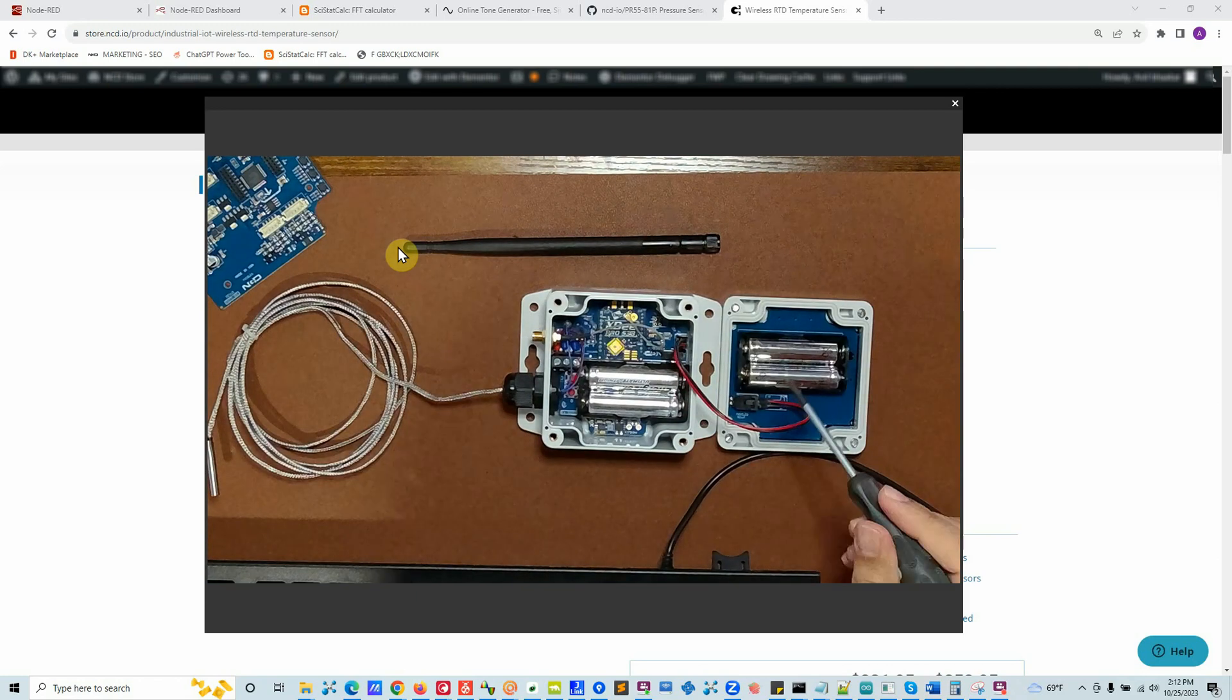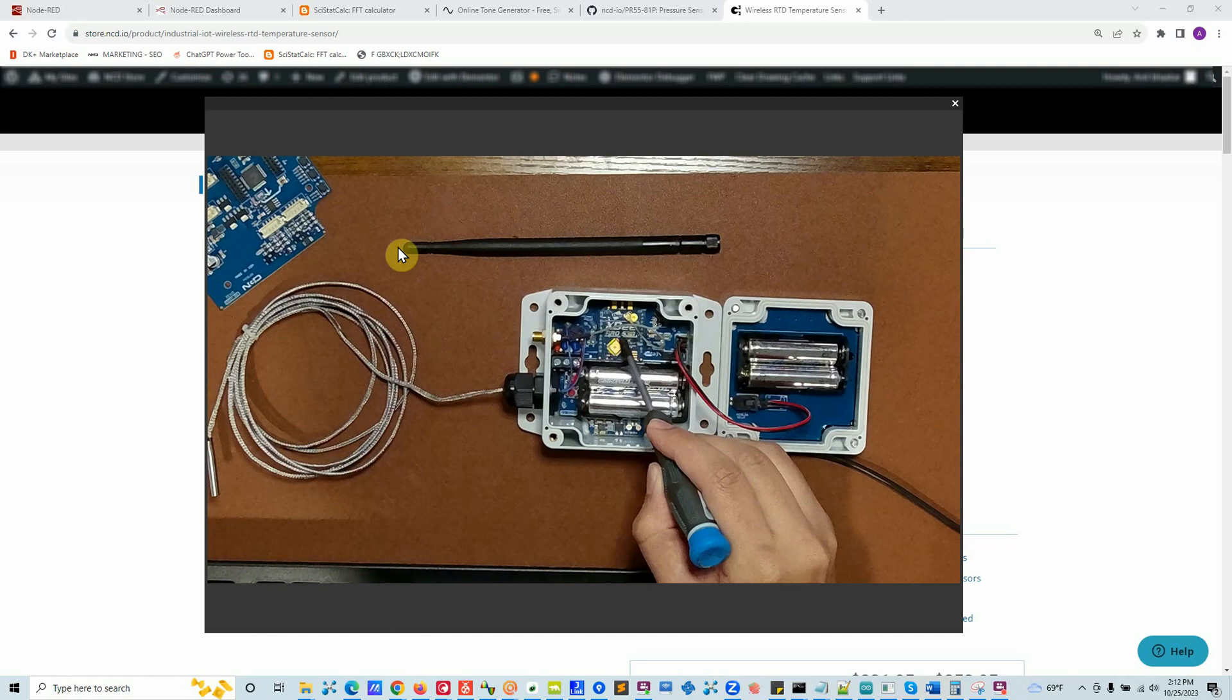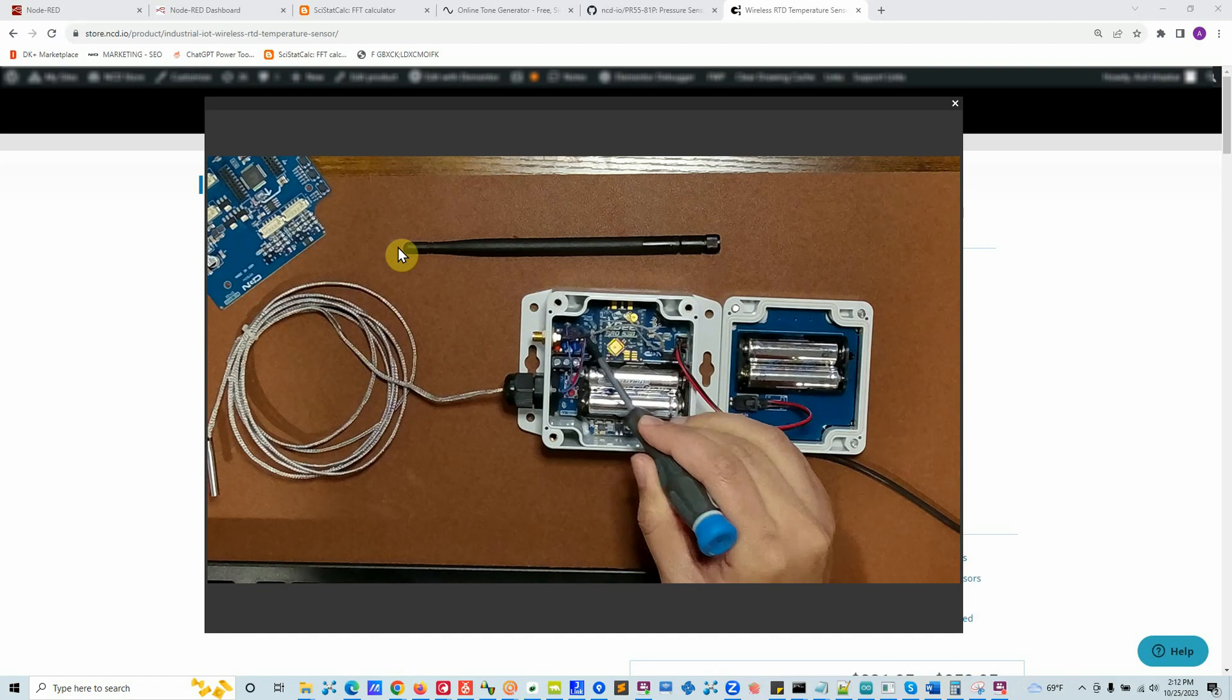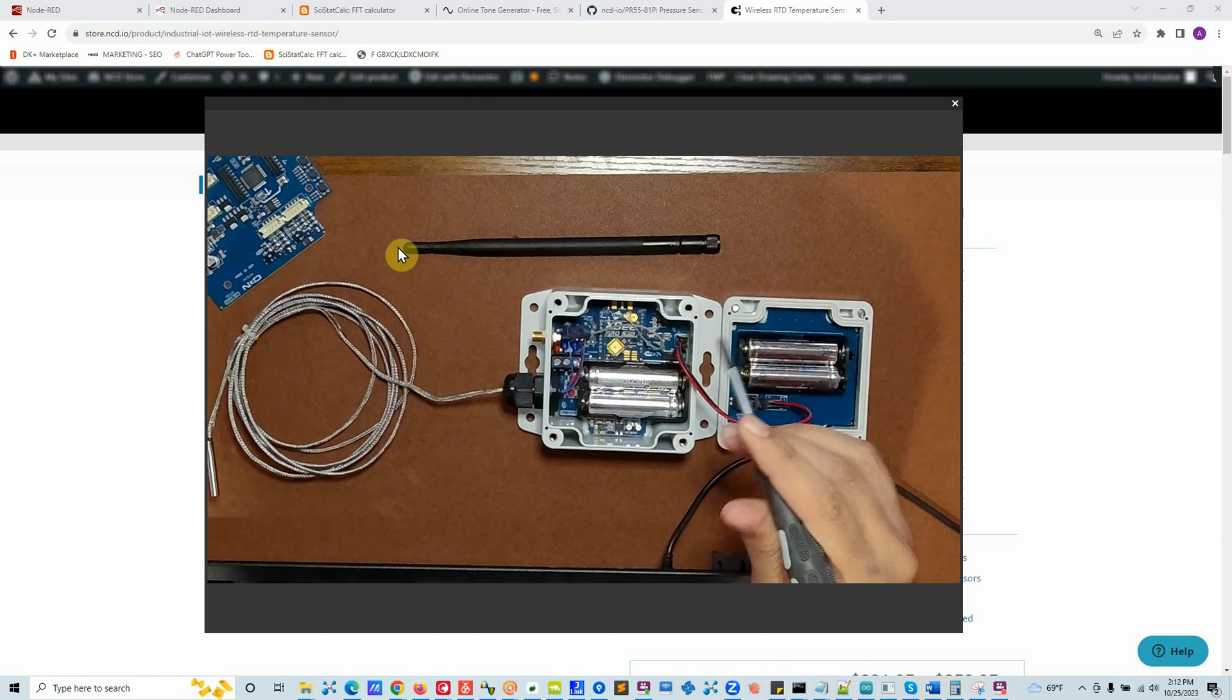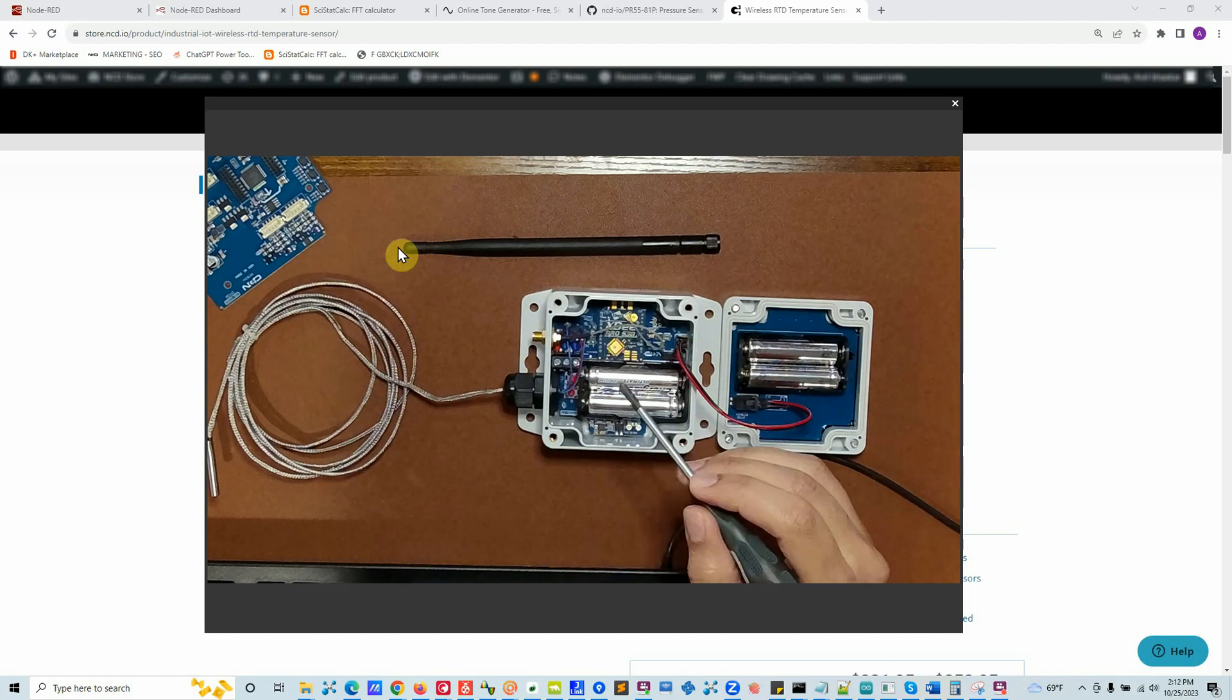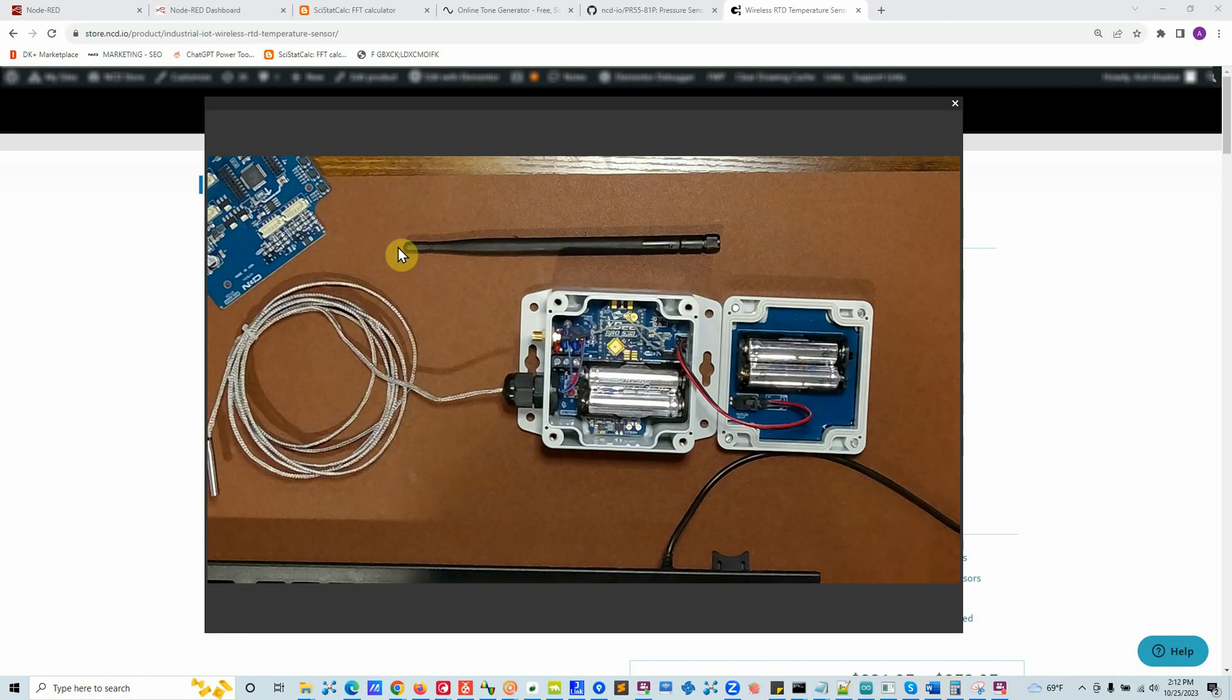Once you open it, you will see, like most NCD sensors, it's got two batteries in the lid and two batteries in the main box. Then it's got a radio module, a switch, power supply, CPU is under the radio module, the RTD chip, three screw terminals to connect to the RTD, and then there are two buttons: one is reset, one is config. Every time you press reset, the device will send a run message followed by a data message. The config button can be used to put the device into configure mode or to factory reset. That's about the hardware part. Let's talk about the software.